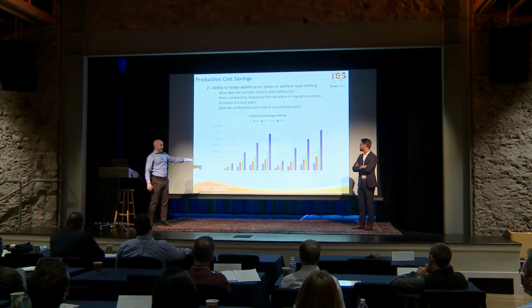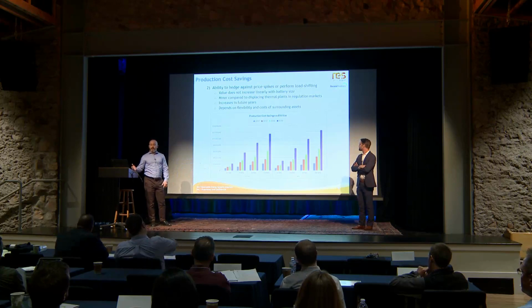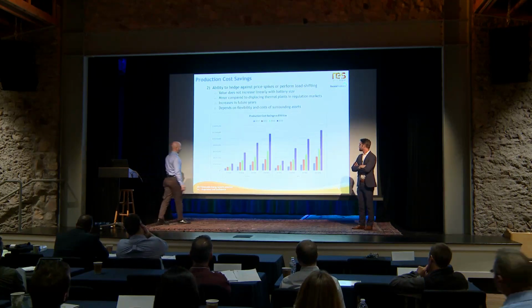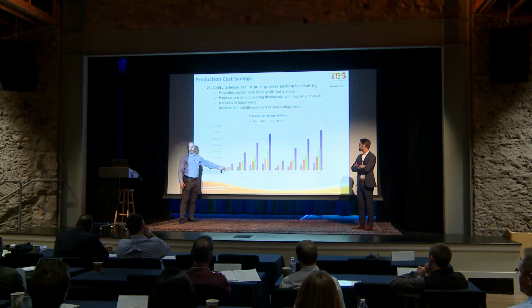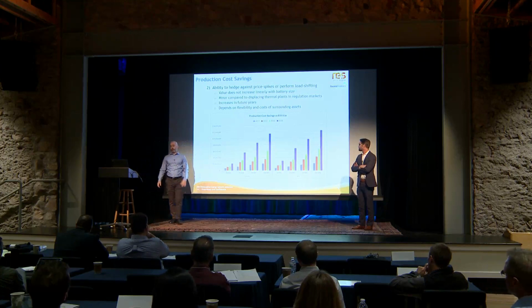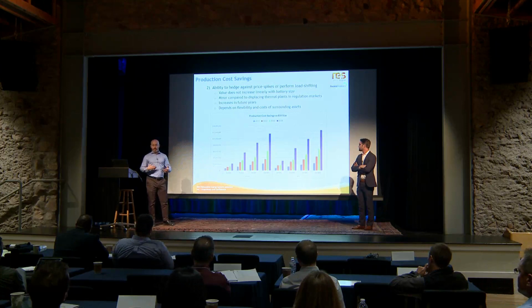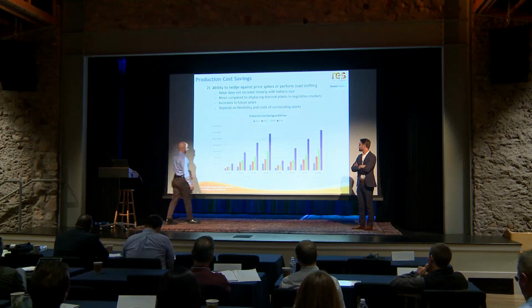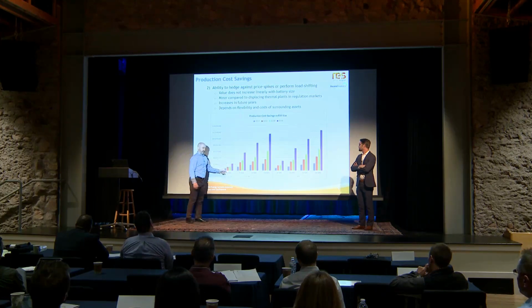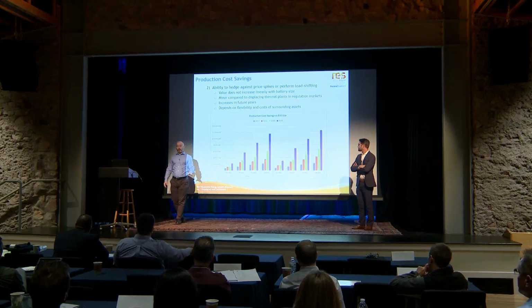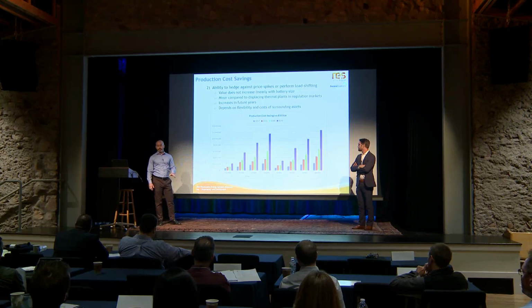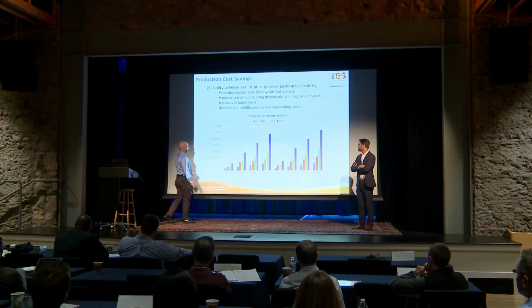The 100 megawatt battery could too, but it also covered some other cases that maybe were not quite as bad. It's still better that we had the battery, but not quite as big of a deal. So we got a lot of value up front just from taking care of the worst avoided cost situations with a smaller battery. Now, they did also do some energy shifting, and that's another reason why the 100 megawatt battery is worth more than the 10. But the regulation was really worth much more in this case, being able to cover those avoided cost situations. That's kind of my takeaway here.